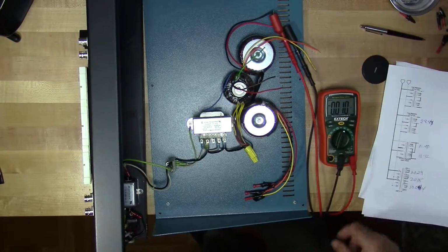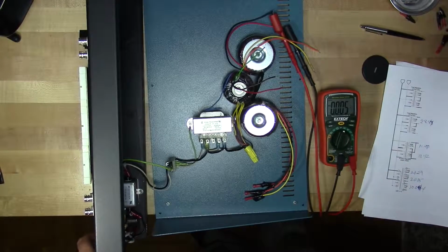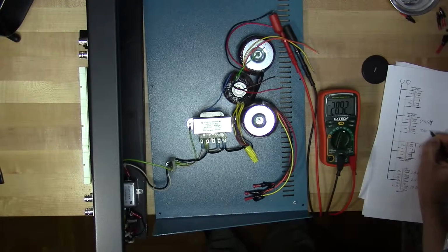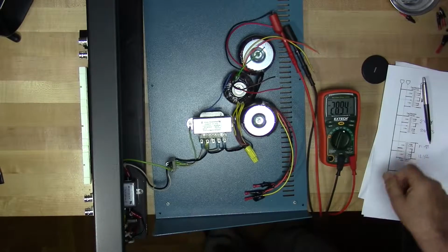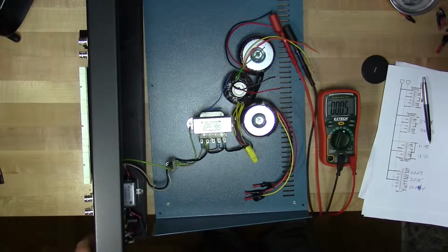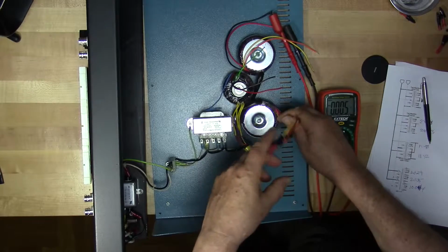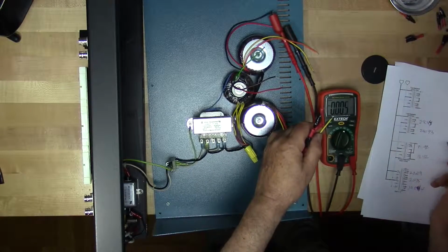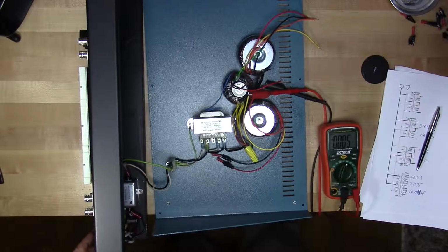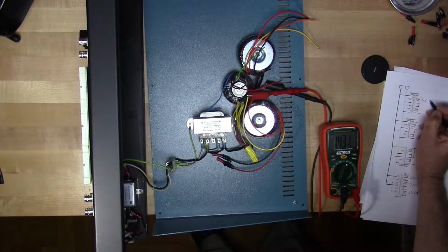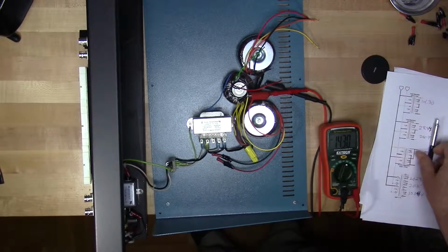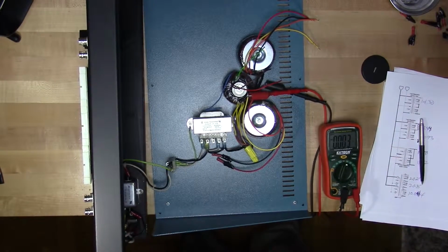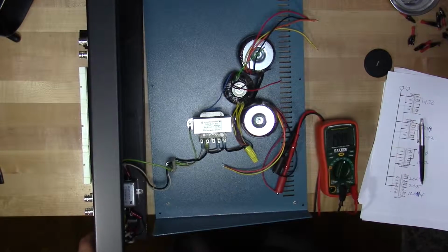The voltages here tend to be a little higher than the manufacturer's specifications. That should be 12. It's 14.3. They're all about anywhere from 10% to 20% higher than the manufacturer's RMS readings.